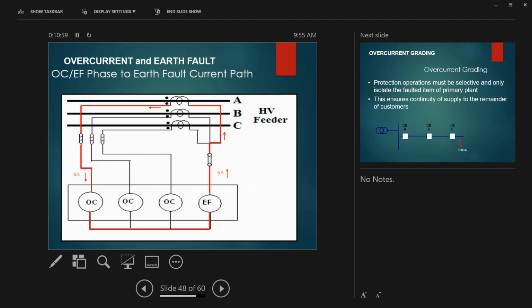Yeah. So there's another way as well. Like, say some people say, okay, this one's creating a problem. I want to trip this, but this one is creating a problem. Since you have access on your laptop, I will disable that earth fault for the time being and inject without changing my connection on the relay. So that's the time that I can test this overcurrent. If I enable this one, that's the time I can test the earth fault as well, because this one will trip first. So there are so many things; it's up to you how you understand the system and how you understand the software.